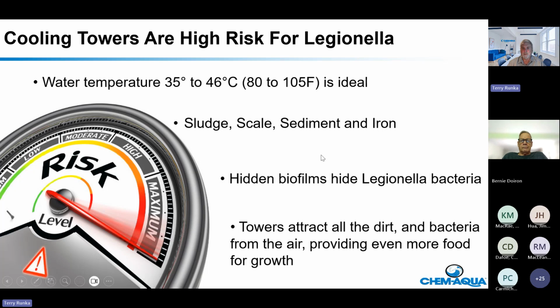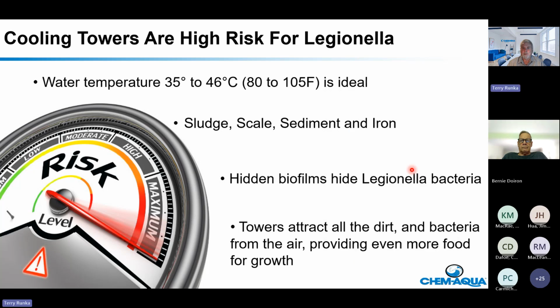I'm going to put my laser pointer out, there we go. Sludge, scale, sediment, iron - there's always lots of food in a cooling tower for bacteria to grow, even Legionella bacteria. There's always hidden biofilms, and we're going to talk about that because that's really important to Legionella control. Towers are big old air washers, they suck all the dirt in the neighborhood in, including bacteria from the air, which provides even more food for Legionella bacteria growth.